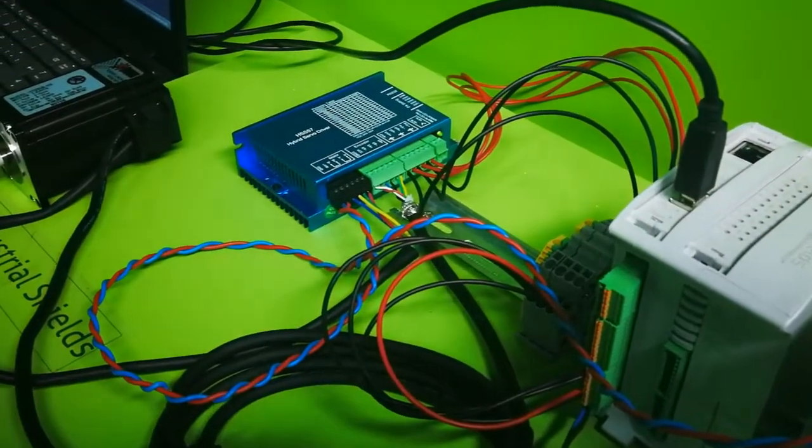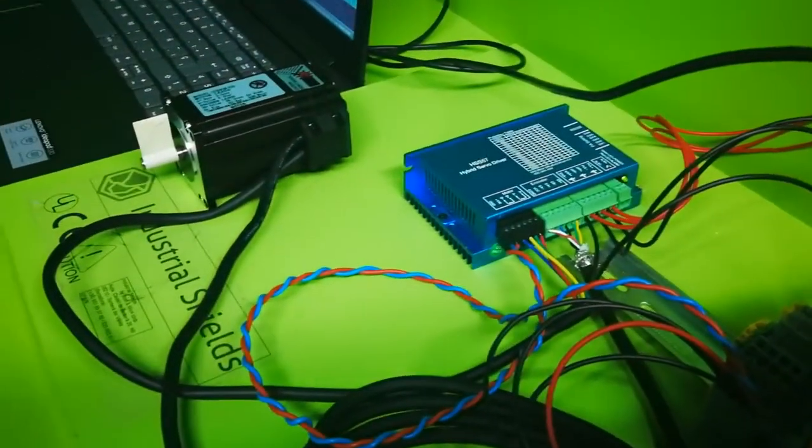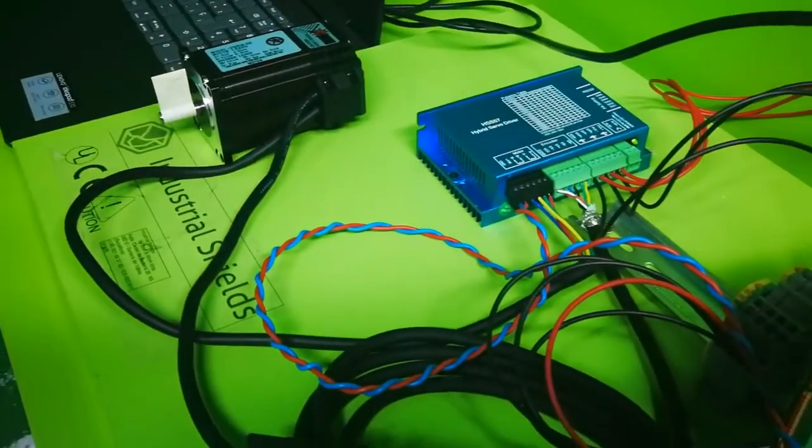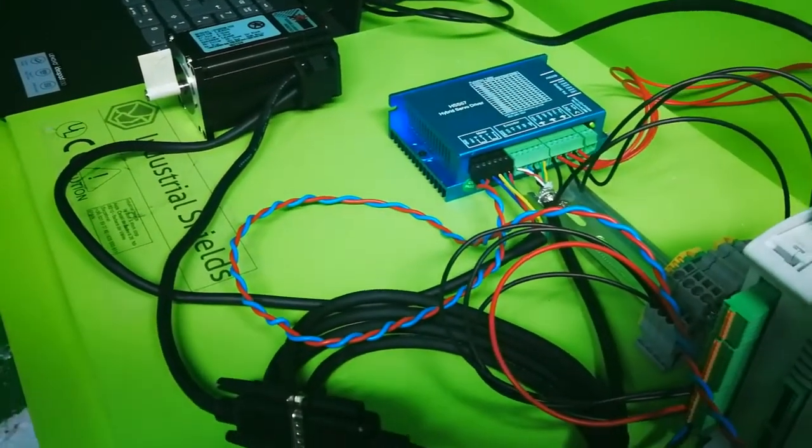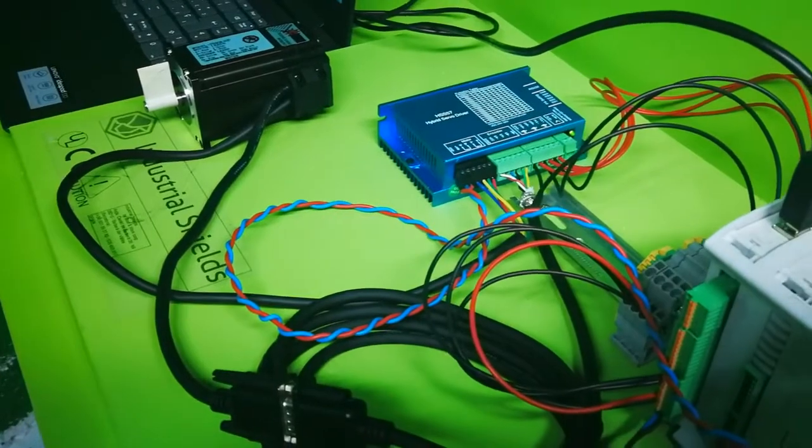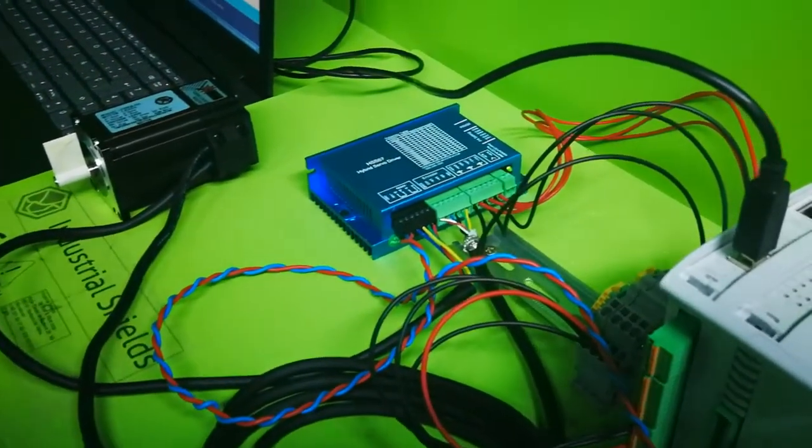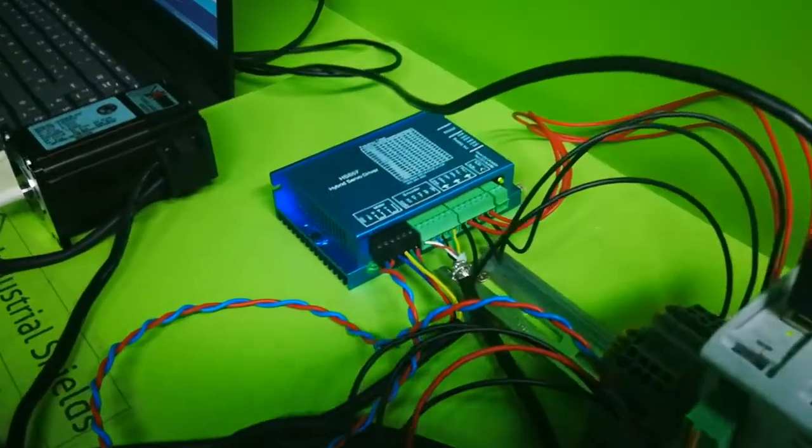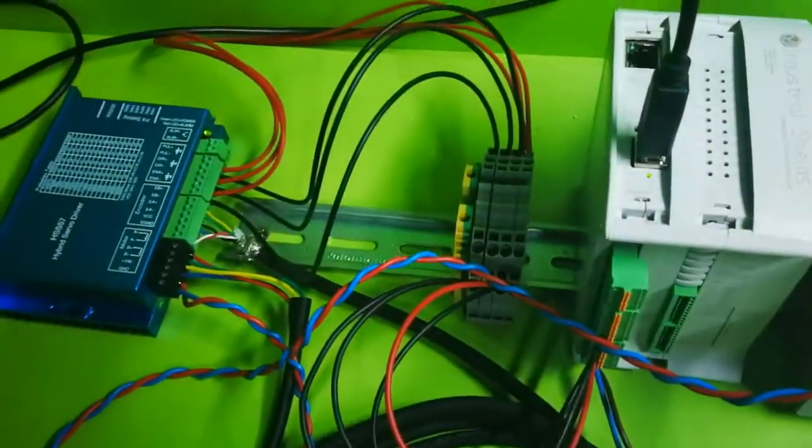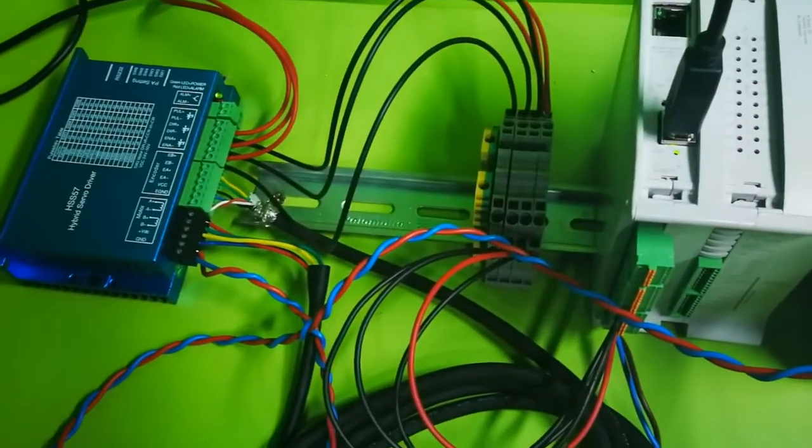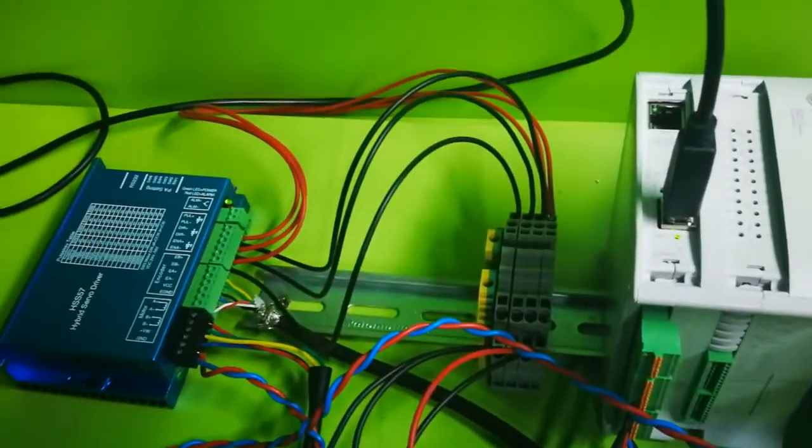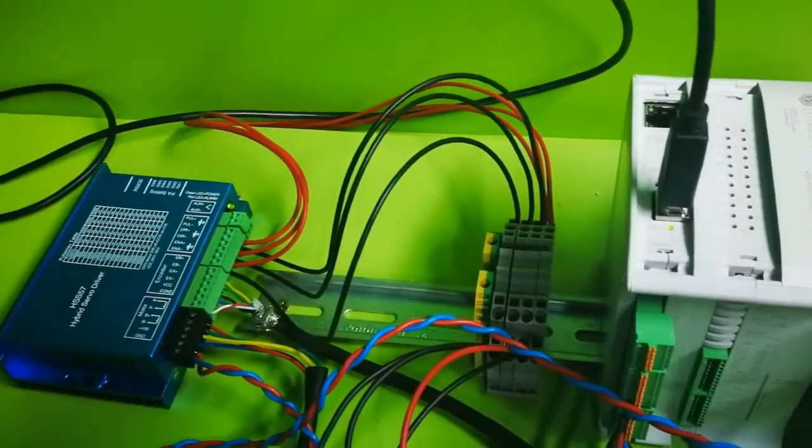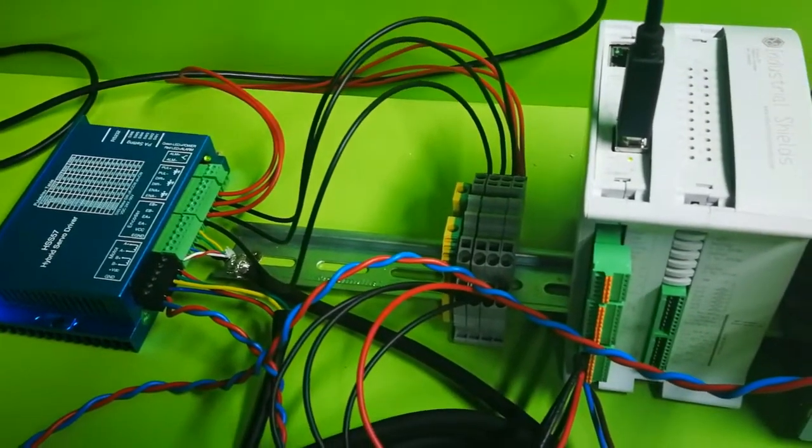We have the servo motor well connected to the servo driver. In this case the servo driver is an HSS 57 hybrid servo driver. We have PULL for pulses, DIR for direction and ENA for enable.